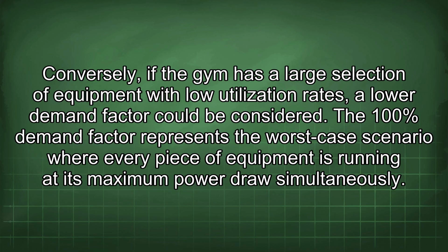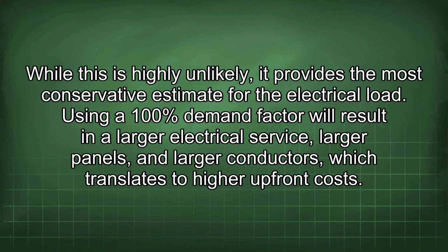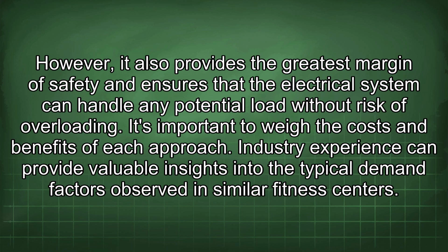The 100% demand factor represents the worst-case scenario where every piece of equipment is running at its maximum power draw simultaneously. While this is highly unlikely, it provides the most conservative estimate for the electrical load. Using a 100% demand factor will result in a larger electrical service, larger panels, and larger conductors, which translates to higher upfront costs. However, it also provides the greatest margin of safety and ensures that the electrical system can handle any potential load without risk of overloading.